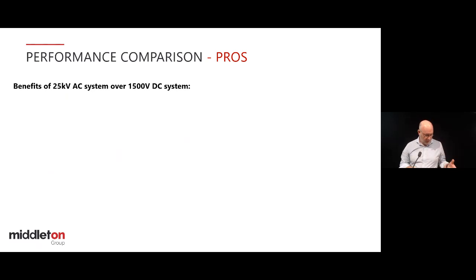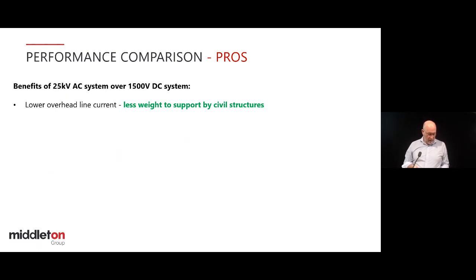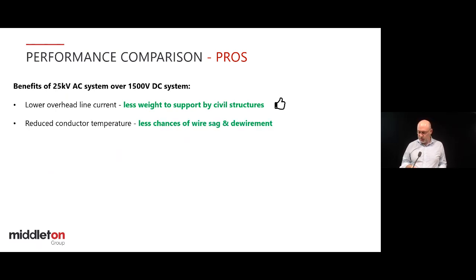So Stephen talked about some of the specific benefits of the different types of system, but overall, 25 kV versus 1500 volt systems gives lower line current. There's a reason why high amounts of power are transmitted at high voltages. You get less current, the P equals V times I equation. So if less current is required to be supported in the conductors, you've got smaller conductors and less weight to be supported by the structures, and that applies to the wind loading, not just the static loading. That's a good thing. Reduced traction currents in the overhead system generally means reduced conductor temperatures, which means less chance of wire sag, dewirement, and annealing of copper conductors.